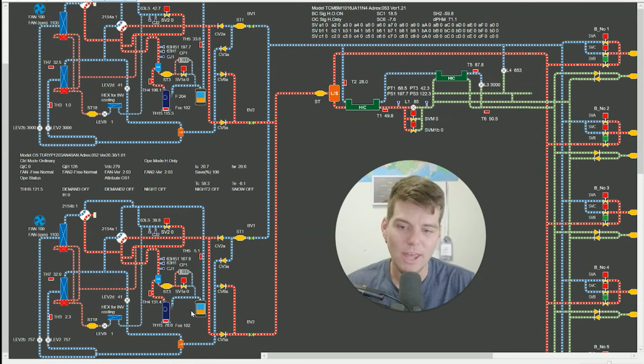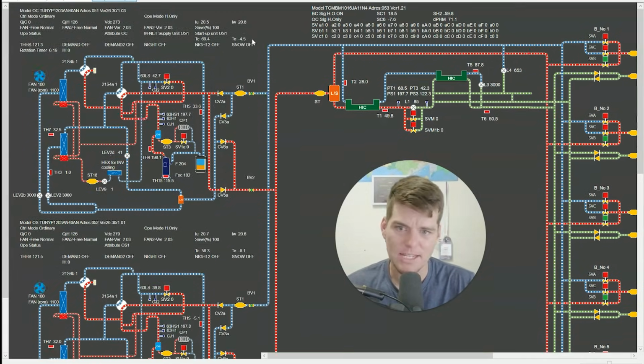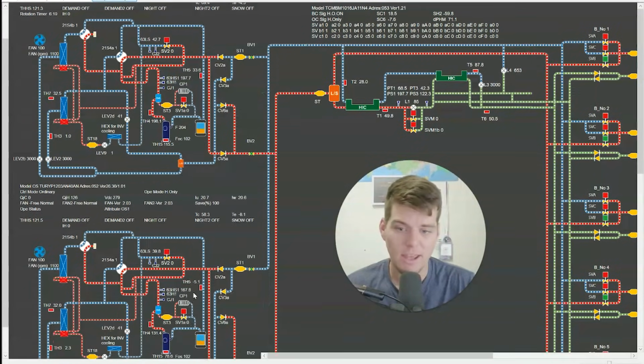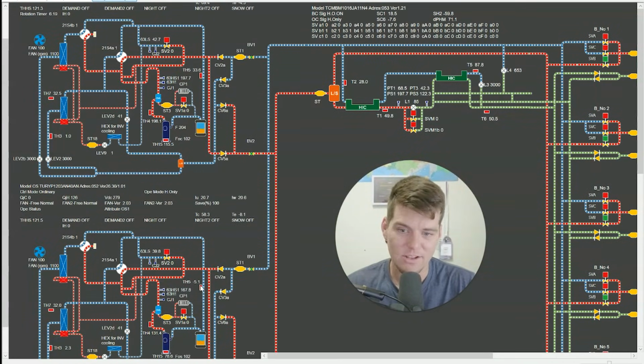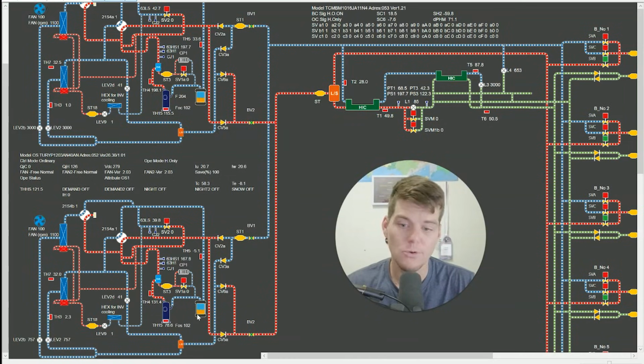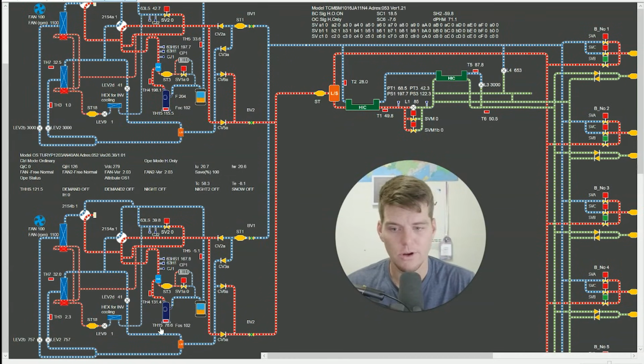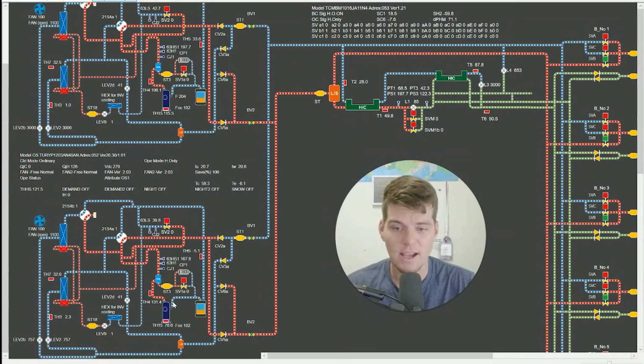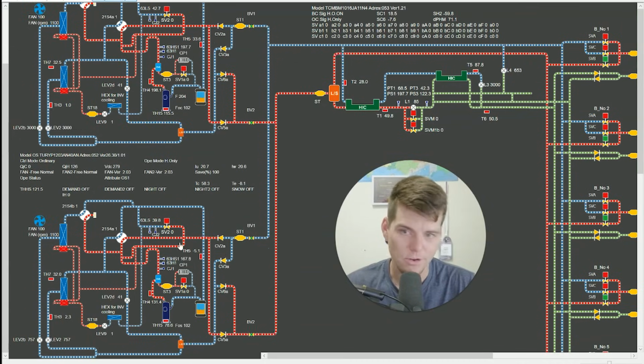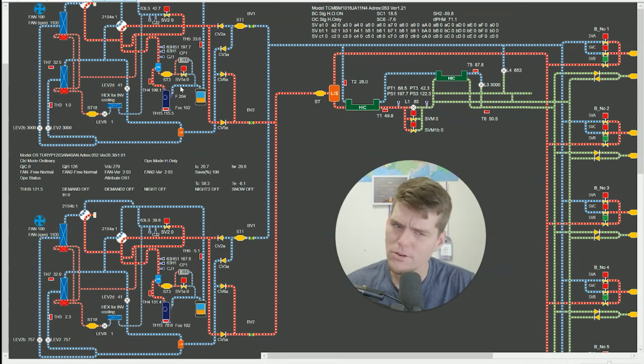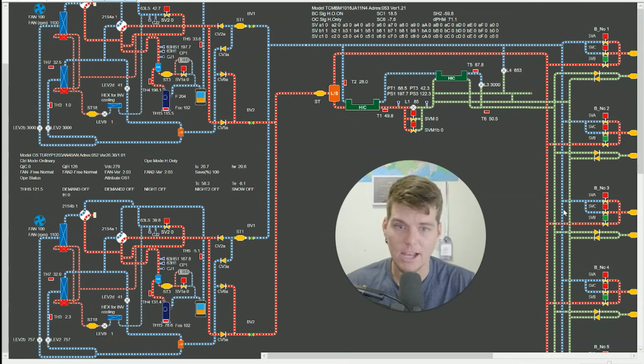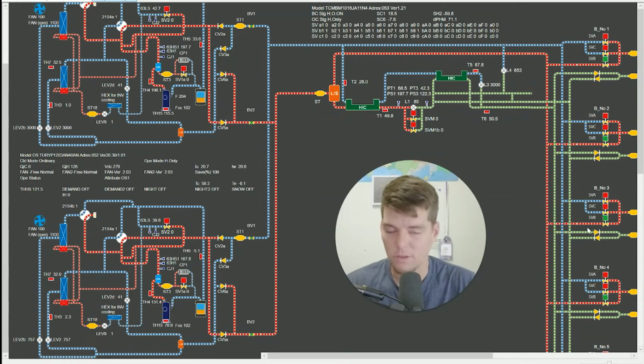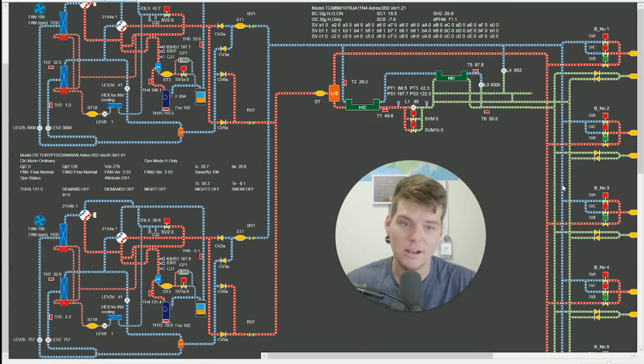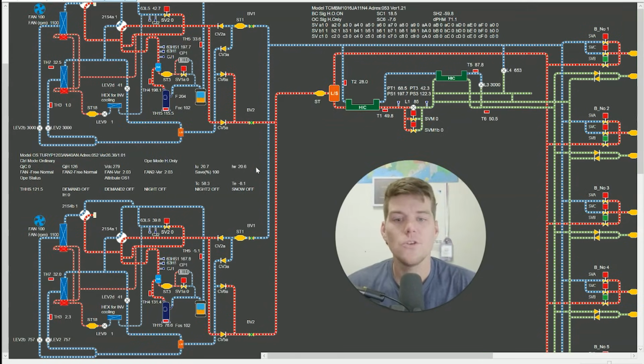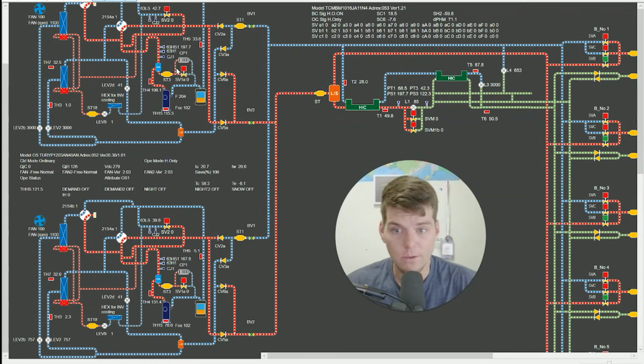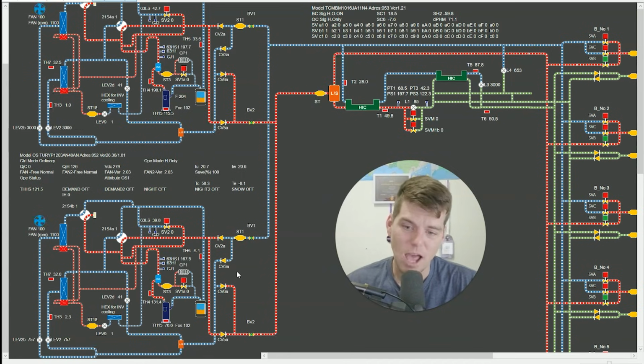So why do they look so different? Why is it that my TE is negative 4.5, but yet I've only got a 1, if not less than that, degree superheat? We know that this low superheat is probably causing our low discharge superheat. And this system over here on this side is acting as if what? It's overcharged. But yet my master module looks like it's undercharged. And my indoor units are starved for hot gas because they need more. They look like they have low subcooling, which tells me that, again, they're not getting enough refrigerant to the indoor units. So why is it that all my indoor units look starved and my outdoor unit looks starved, but my submodule does not look starved?